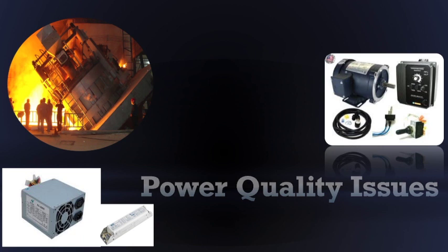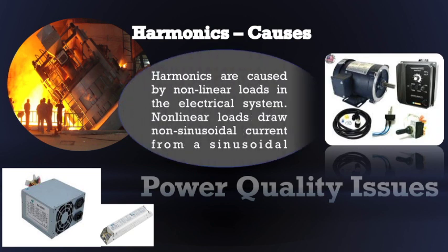Now we will discuss about the causes of harmonics. Harmonics are caused by nonlinear loads in the electrical system. Nonlinear loads draw non-sinusoidal current from a sinusoidal voltage source. Examples of nonlinear loads are AC or DC motor drives, electric arc furnaces, inverters, var compensators, SMPS, etc. Industrial customers are increasingly using drives for more precise motor control and to improve energy efficiency. Consequently, the potential for greater harmonic distortion rises.